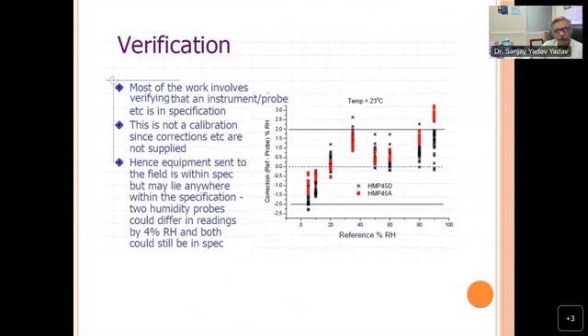Calibration is comparing the reading of an instrument when it is exposed to a known artifact or condition. Either the instrument is adjusted to read correctly or a table of corrections is made, which is basically a method by comparing measurements taken by a measuring instrument against the standard whose measurement uncertainty is known and is traceable to national or international standards. Another terminology in your case is verification. Most of the work involves verifying the instrument, oblique probe, etc. against specification. This is not a calibration since corrections, etc. are not supplied in verification. Since equipment sent to the field is within specification but may be anywhere within the specification. So this is an example of that verification thing.